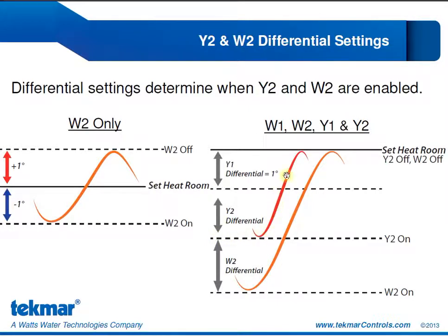Our Y2 differential can be programmed. You have a 0 to 4 degree range. So Y2 will turn on when we are 1 degree plus the Y2 differential below the set heat room setting. And it won't turn off until we reach the set heat room setting. Our W2 differential is also configurable. It goes from 0 to 8 degrees. W2 will turn on when we are 1 degree plus the Y2 differential plus the W2 differential below the set heat room, and it won't turn off until we're at the set heat.